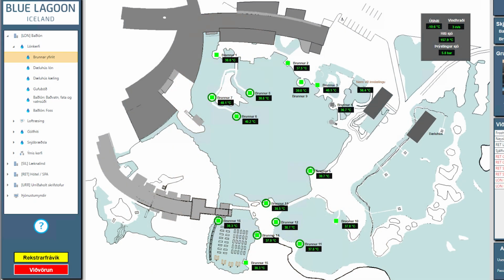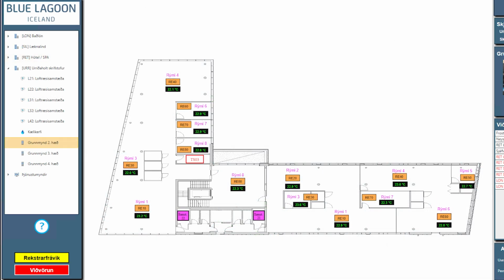And then we took the old displays, converted them to Gen 64 with ConvertWorks. We stripped out the templates. We changed the dimensions for the remaining contents to match the new embedded display. And then we renamed the new displays using a kind of unified naming convention, so it's much easier to browse and maintain. And we actually made quite substantial changes to the graphics, so that colors and elements are meaningful and have the same meaning throughout the system.